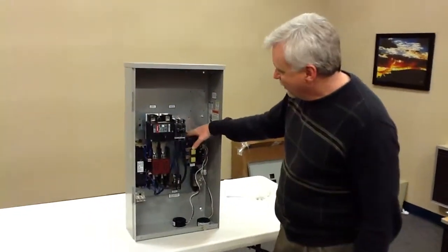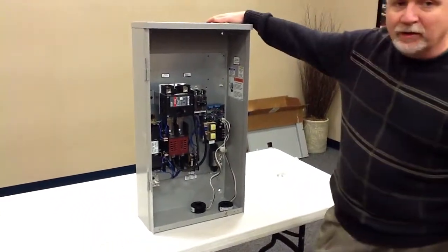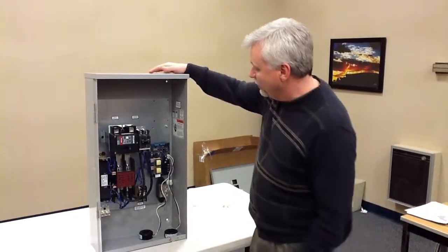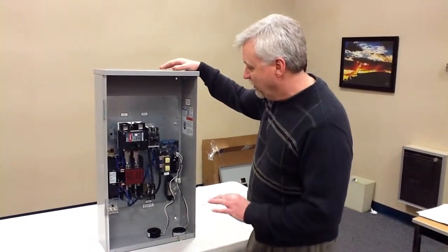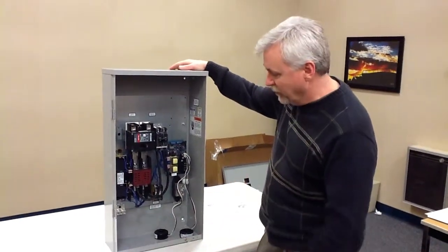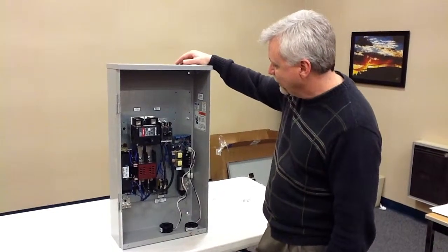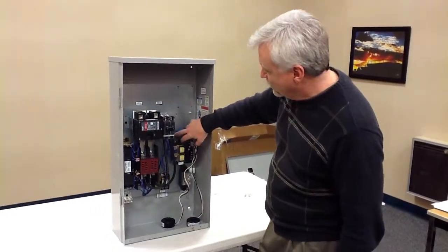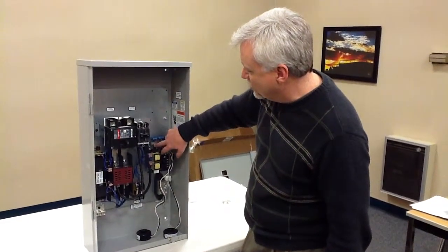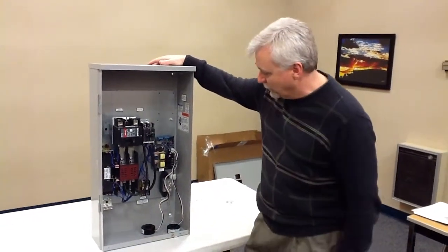We have an air conditioning control module board that's installed in every one of our transfer switches with the exception of our 50 amp. And what this does is there are three determining factors that allow you to properly manage your load under National Electric Code NEC 702.5 and still call whole house power. First of all, you have dip switches here that will, when flipped in the proper positions, indicate the size of the generator that is installed with this transfer switch.